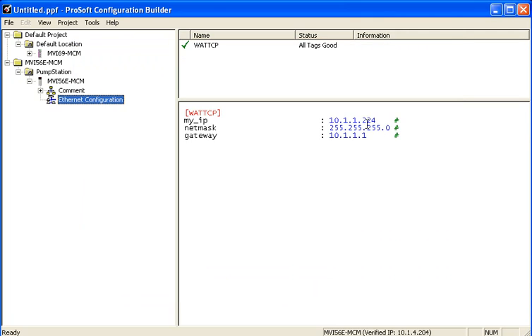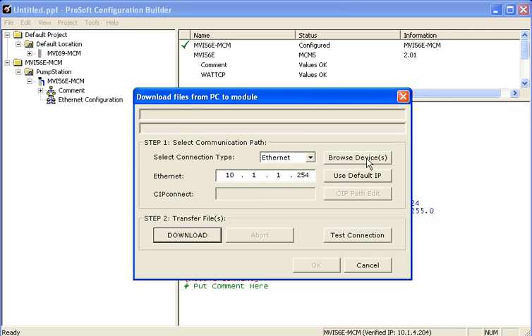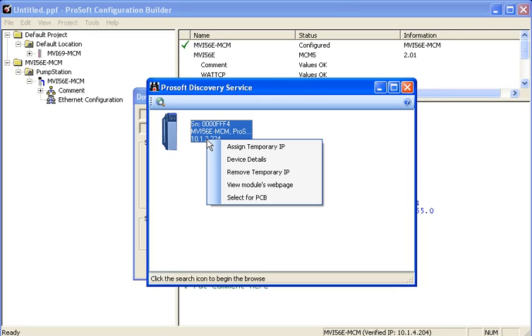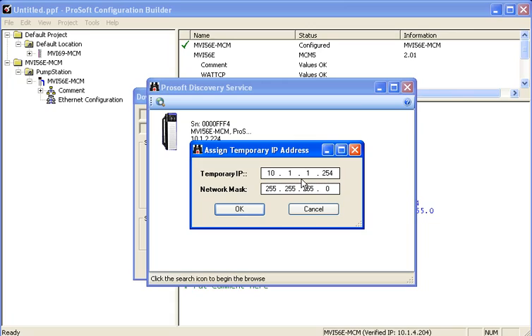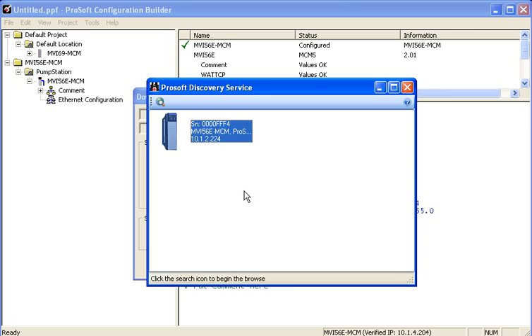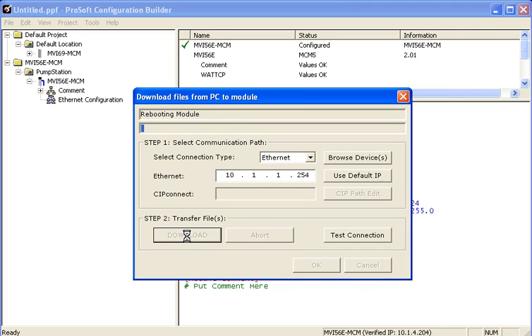OK, now that I have the IP entered in, I'll right click on the device name, choose download from PC to device. And now I'm going to click on browse devices. And since the module is using an IP address that's out of my subnet range, I'm going to assign a temporary IP address. And the software automatically enters in a temporary IP address. Click OK. Now I'll right click and I'll select for PCB. And we'll close the discovery window. And you'll notice that the temporary IP address is in there. Now I'll click download. And you see that our download succeeds and our module is running.